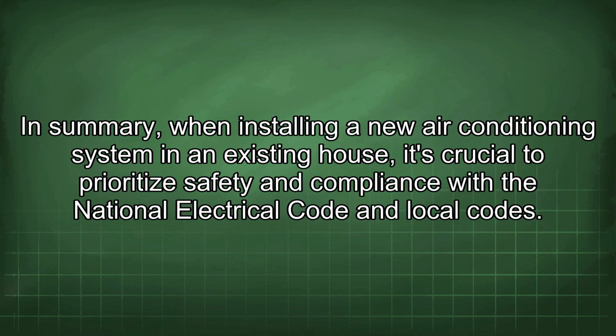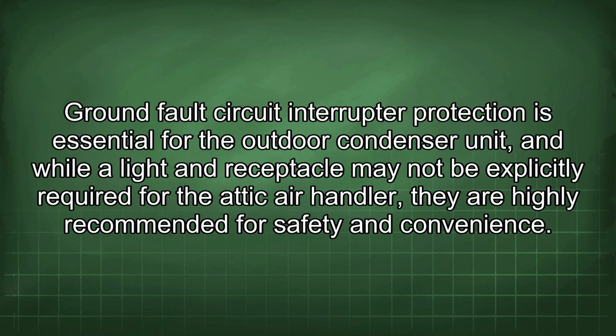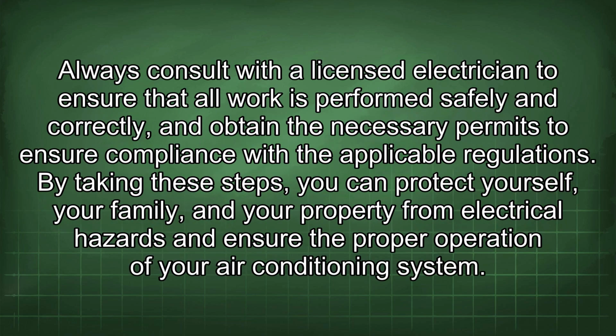In summary, when installing a new air conditioning system in an existing house, it's crucial to prioritize safety and compliance with the National Electrical Code and local codes. Ground fault circuit interrupter protection is essential for the outdoor condenser unit, and while a light and receptacle may not be explicitly required for the attic air handler, they are highly recommended for safety and convenience. Always consult with a licensed electrician to ensure that all work is performed safely and correctly, and obtain the necessary permits to ensure compliance with the applicable regulations. By taking these steps, you can protect yourself, your family, and your property from electrical hazards and ensure the proper operation of your air conditioning system.